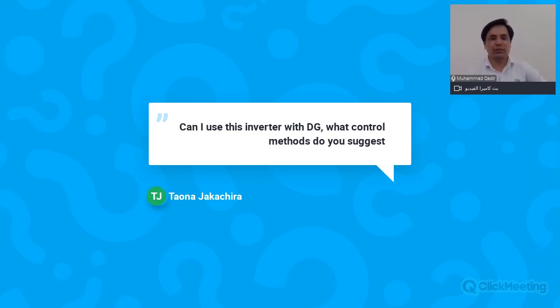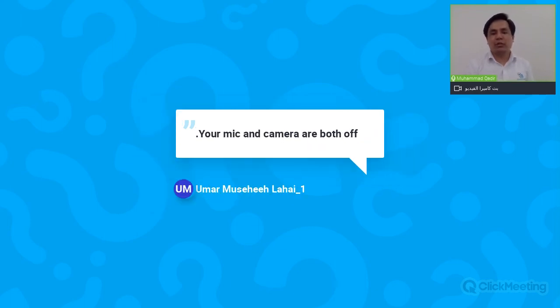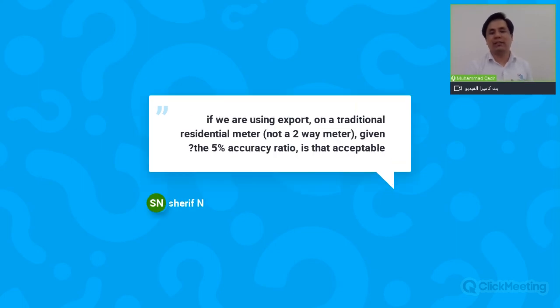So next question, can I use this inverter with DG? What control methods do you suggest? If you mean diesel generator by DG, then yes, you can use, and you will be needing a hybrid controller, as I said earlier, and thus you can use Huawei inverters in parallel to diesel generator and make a hybrid PV system with generators. The hybrid controller will make sure that your generators are running within their minimum rated load, and thus their life is not affected.